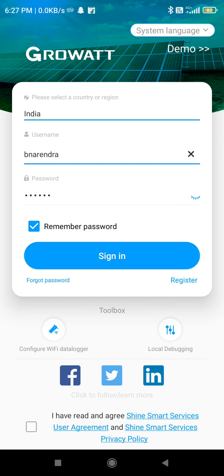Hello guys, in this video I am going to show you how to change Growatt AC site parameters, grid parameters. Frequently the error "AC voltage outrange" appears on the display, and we used to call a service engineer. Here we can change the grid site parameters using the Shine Phone application itself, but the inverter should be online and the data logger should be configured, okay?